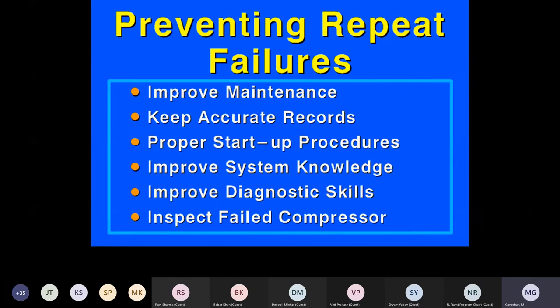The startup procedure is very, very important. For any new chiller, any system, even a small system, the initial startup process is very, very important, including flushing the systems and completely checking the water quality. There are many things which can lead into a cataclysmic effect, leading into the compressor failure. This system knowledge should be there: what it is designed for, how much we can load it, the maximum overload.